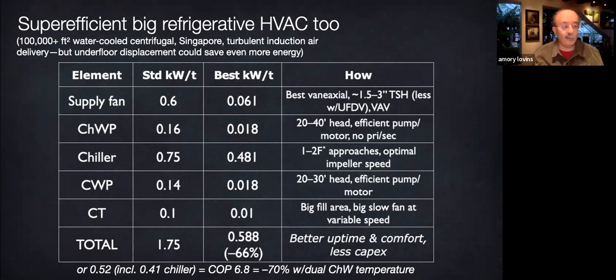So all this adds up to 0.588 kilowatts per ton at the Singapore design hour, or down to the bottom, 0.52 if you use 2 separately optimized cooling coils at 4.5 Celsius for condensing, that is for drying the air, and 12 for sensible cooling. So all that raises the total energy saving to 70% from supposedly good normal practice at lower capital cost with better comfort. This practice spreads slowly to engineers whose fee is a percentage traditionally of the cost of the equipment they specify.